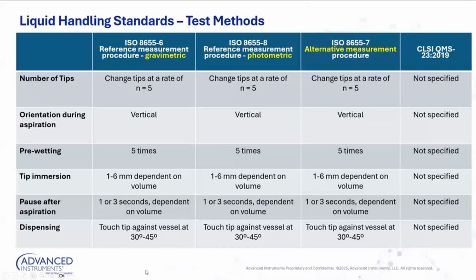All right, so not only does the environment come into play when it comes to following ISO standards for pipette calibrations and verifications, but also the method comes into play, specifically how you are operating the pipette. If you take a look across the top, I've got the reference measurement procedure for 8655 Part 6, which is for gravimetric testing, Part 8, which is for photometric testing, Part 7, that's the alternative measurement procedure, which follows a lot of what Parts 6 and 8 mention but has a little bit more flexibility for your everyday lab. And then rounding out the end, we've got QMS 23.